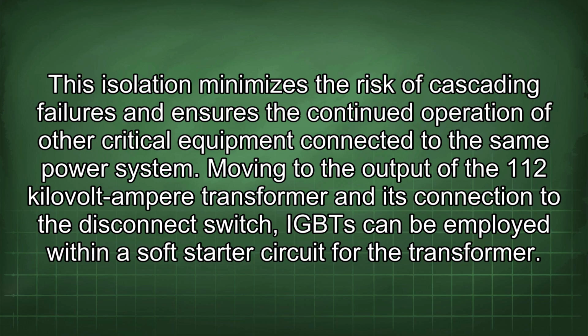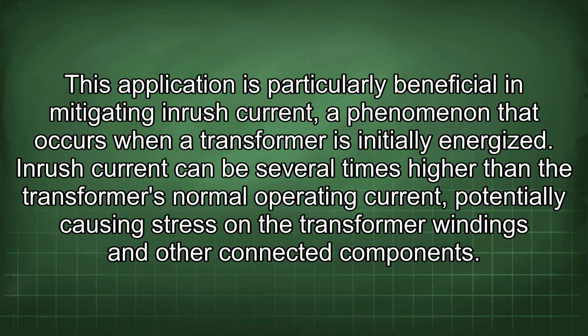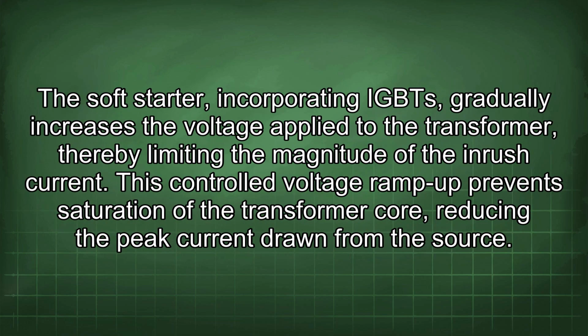IGBTs can be employed within a soft starter circuit for the transformer. This application is particularly beneficial in mitigating inrush current, a phenomenon that occurs when a transformer is initially energized. Inrush current can be several times higher than the transformer's normal operating current, potentially causing stress on the transformer windings and other connected components. The soft starter, incorporating IGBTs, gradually increases the voltage applied to the transformer, thereby limiting the magnitude of the inrush current. This controlled voltage ramp-up prevents saturation of the transformer core, reducing the peak current drawn from the source.